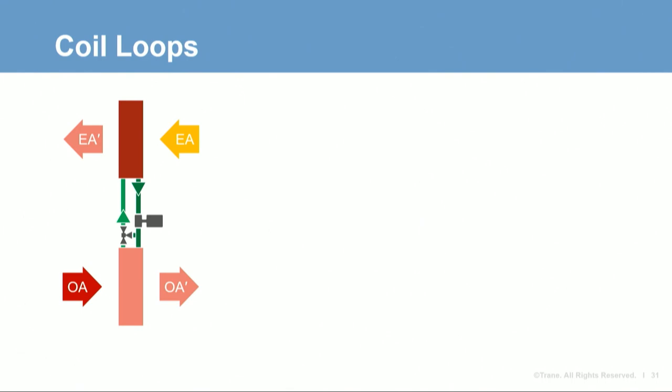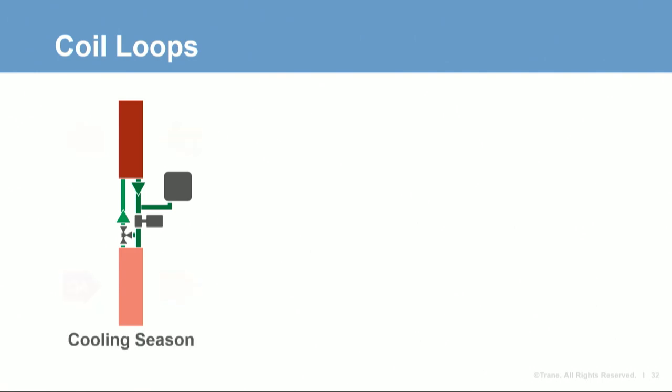A fluid is circulated by a pump between the coils to transfer sensible heat from one airstream to another. The fluid is often water mixed with a freeze inhibitor like glycol, and an expansion tank is needed because the fluid volume will change with temperature. In the cooling season, hot outdoor air enters the building for ventilation, passes through a coil, and the outdoor air is cooled. This warm fluid is circulated to the other coil in the exhaust airstream, where the heat is absorbed by the exhaust air as it leaves the building.